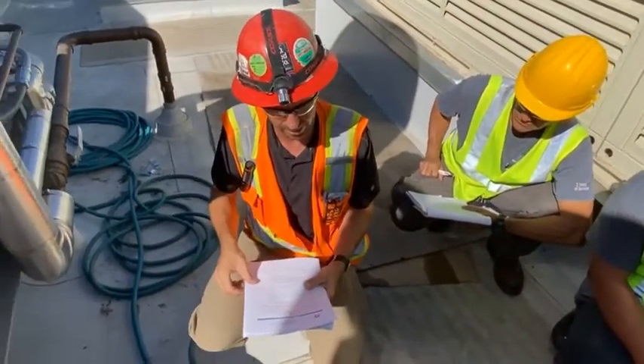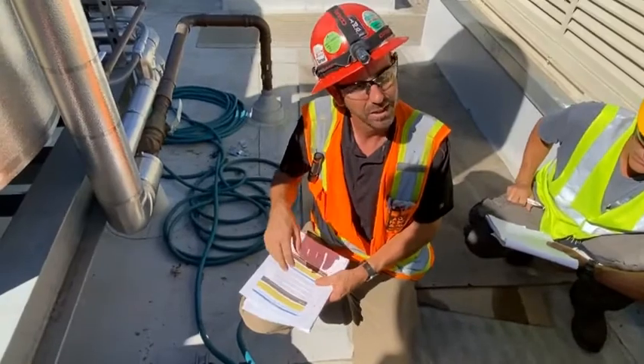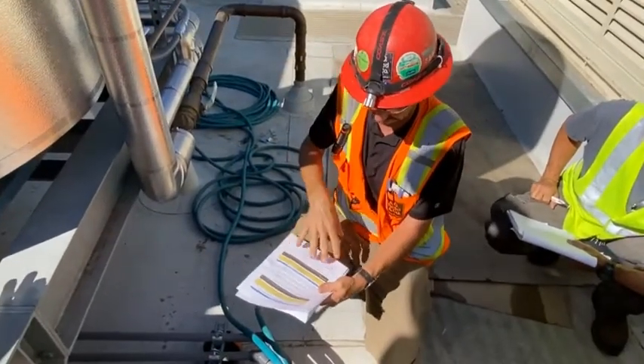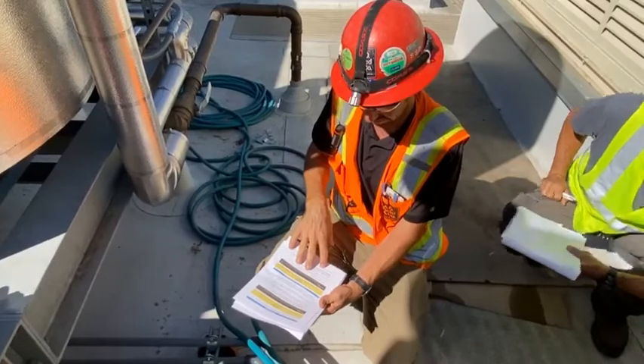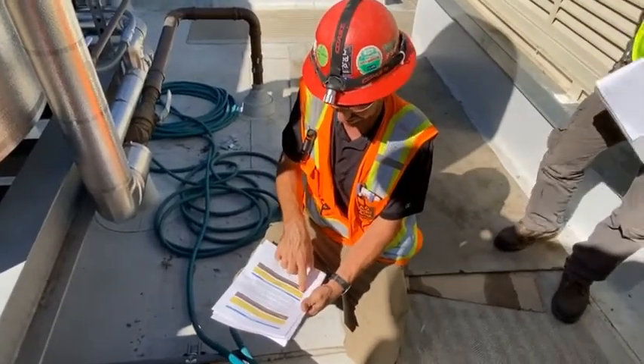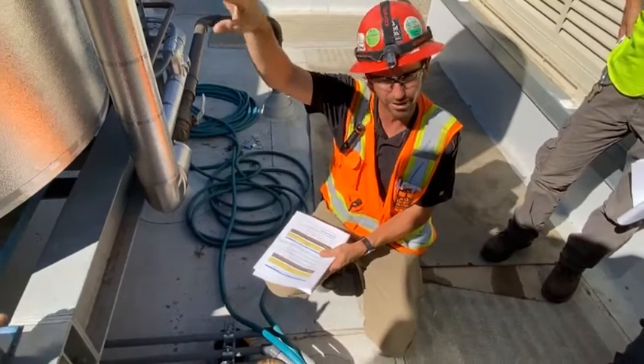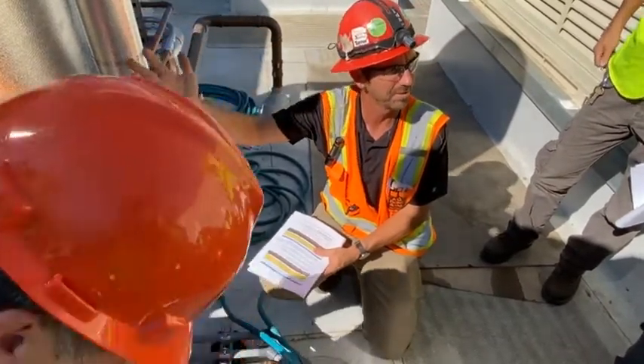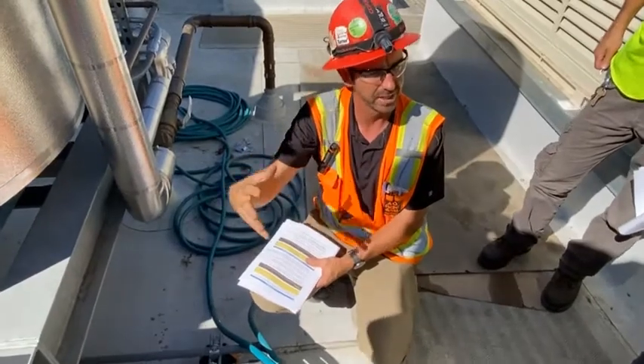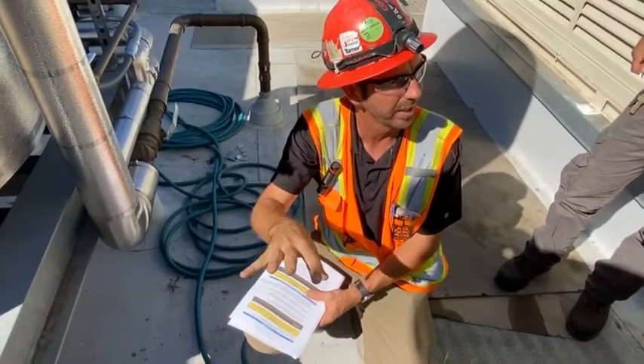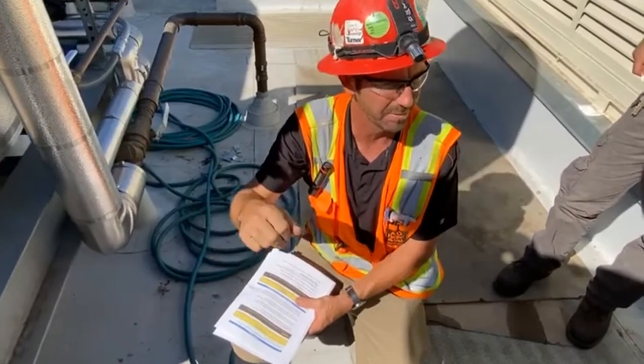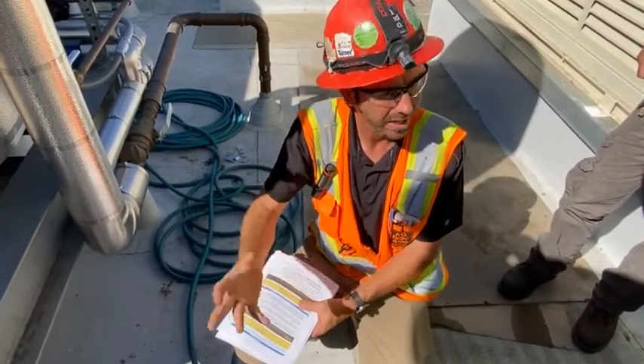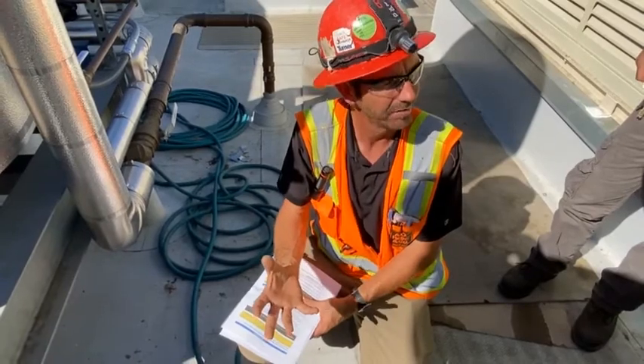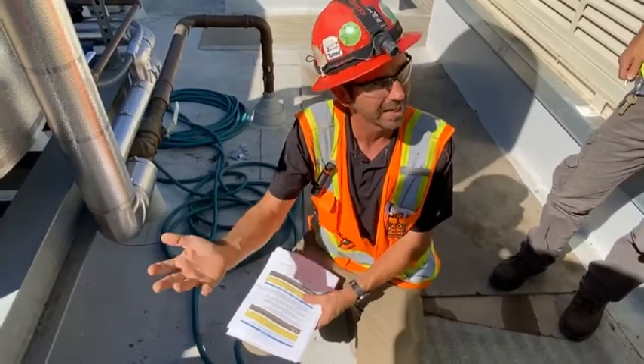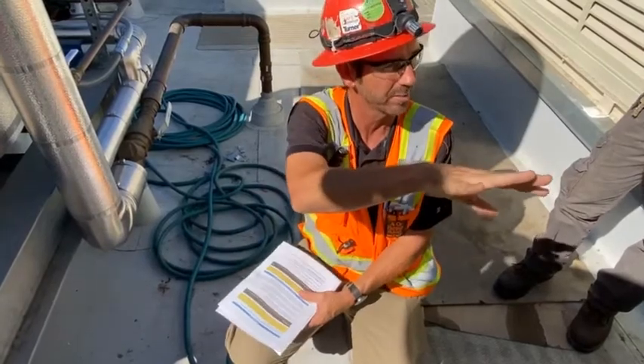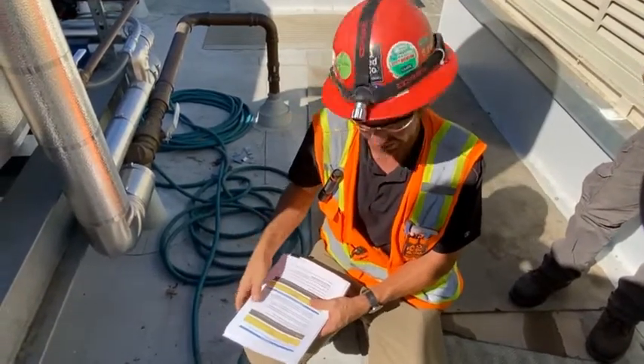which will need to be cleaned. That's an annual cleaning. You'll open up the manway, and there's a procedure on opening the manway in the O&M manual under section C. They give you the procedure on how to open it. Just make sure anytime you open any piece of equipment that might have an O-ring, that you look at that equipment first and order a gasket rebuild kit, because sometimes the gaskets can rip when you open up a device. It'd be better to have that replacement kit on site versus opening it, finding out you ripped a gasket, and now you can't put something back together. Mostly important on the strainers we talked about yesterday and any type of that equipment, okay?